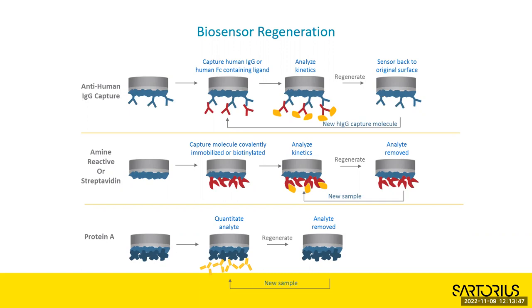The streptavidin biosensors are probably my favorite. If you have a biotinylated molecule binding to the streptavidin biosensor, that bond is not going to come off easily - streptavidin has a binding affinity of femtomolar to biotin, and it's super strong. But what you can do is dip the whole complex into a regeneration solution and pull off the analyte, leaving the ligand still attached. The sensor can be reused as long as the regeneration solution doesn't start to degrade the ligand.